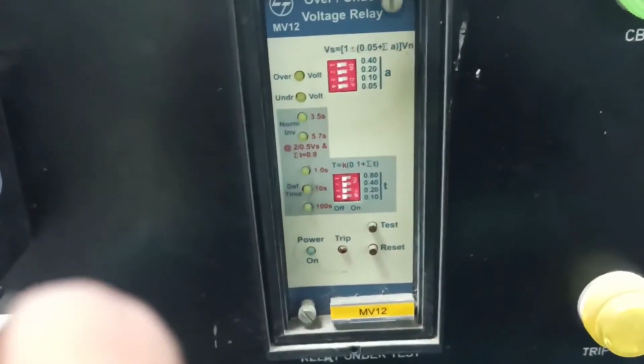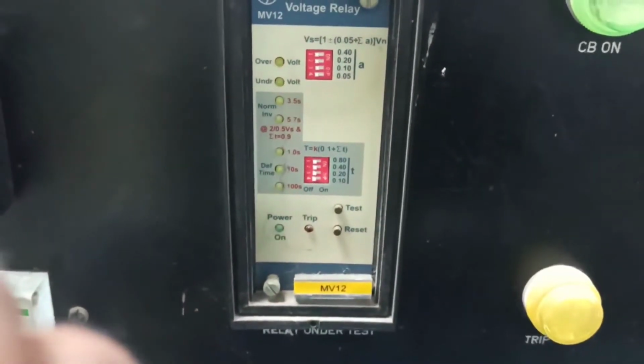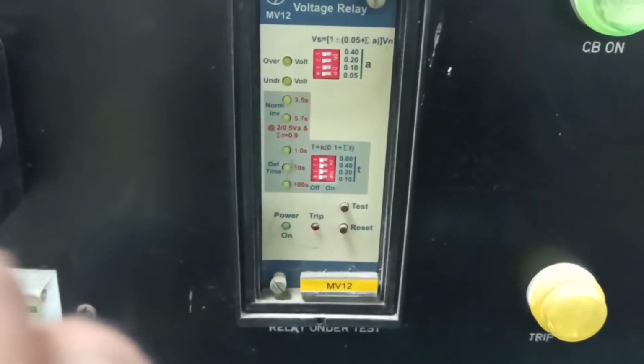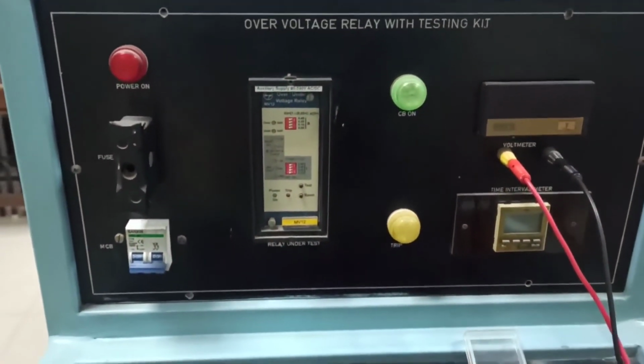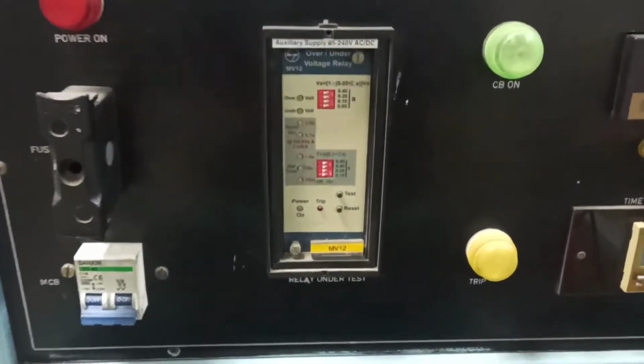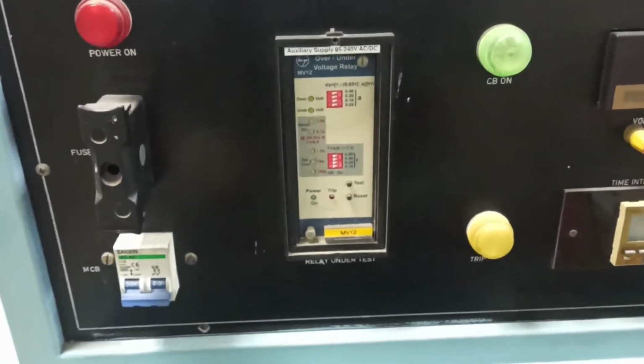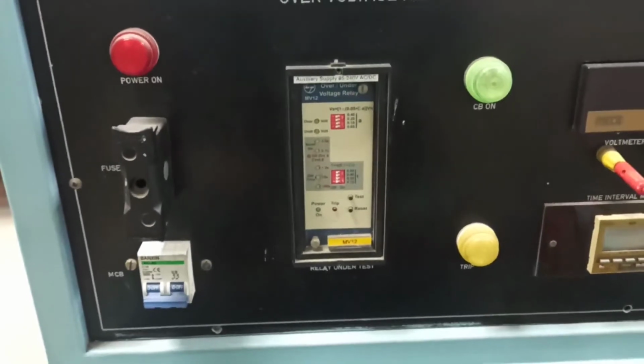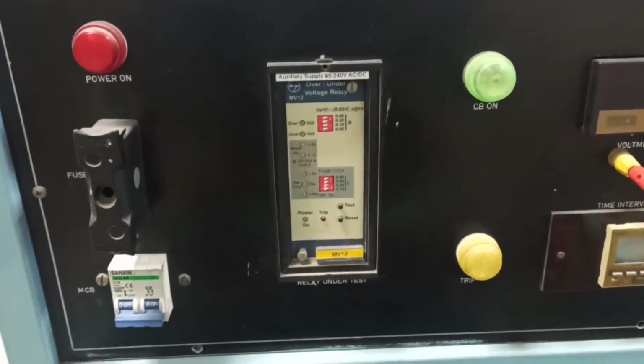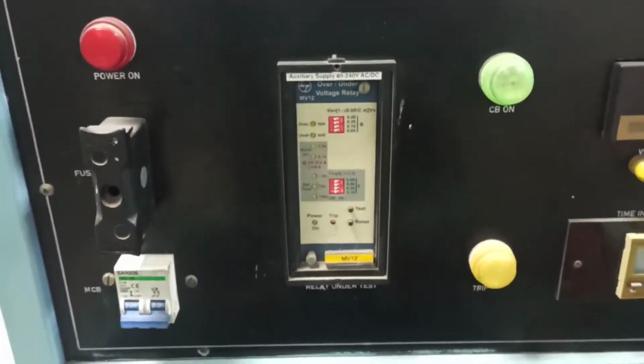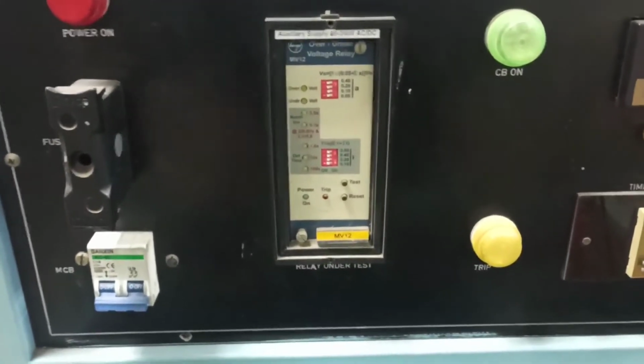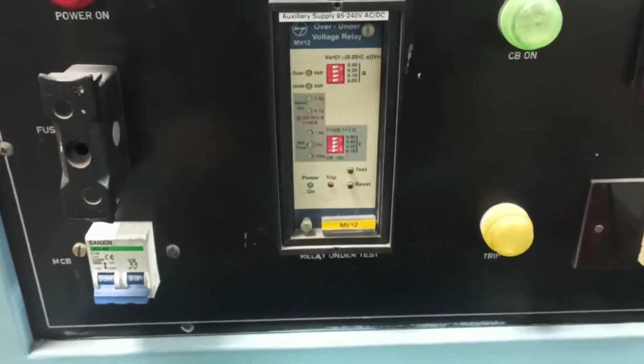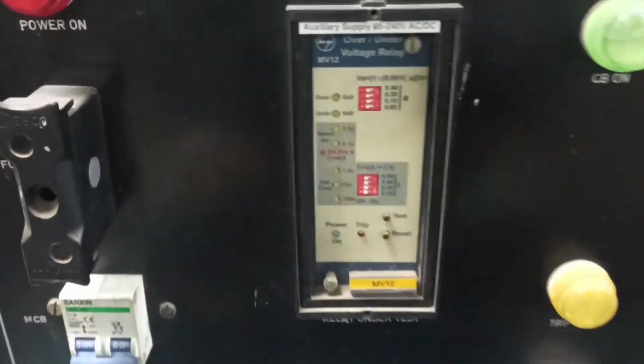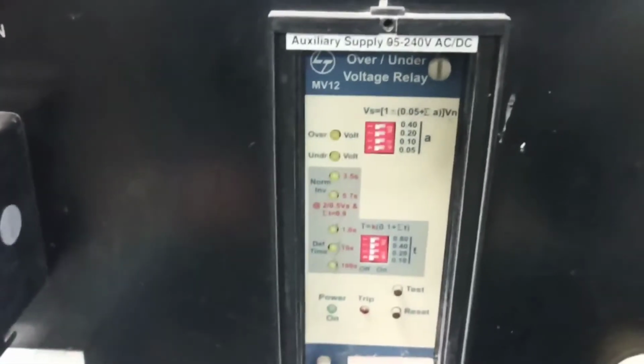And this is your relay. This is the MV12 relay, L&T over voltage and under voltage relay. Over voltage means when your voltage goes above a certain reference voltage, then your relay is going to work. And if your voltage goes below a certain reference, then your relay is going to work. So you can change the settings of this relay. There are settings inside, so you can change whether it is going to work on over voltage or under voltage. Right now it is working as an over voltage relay.